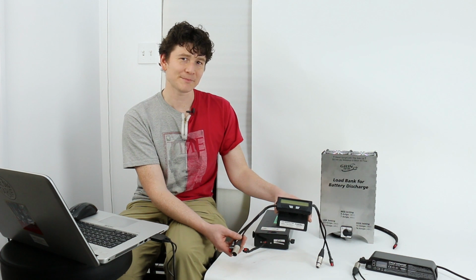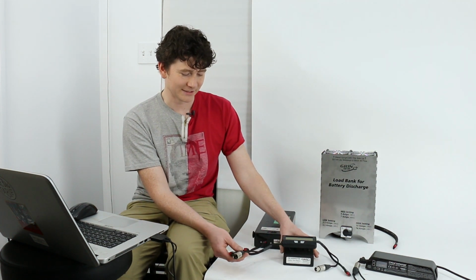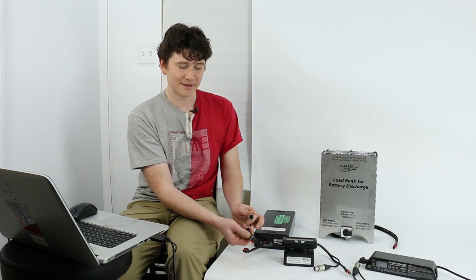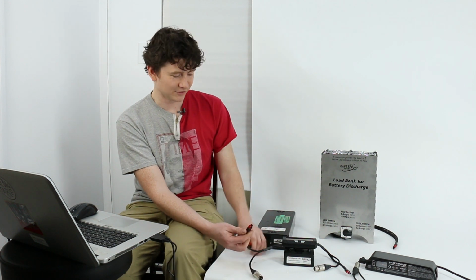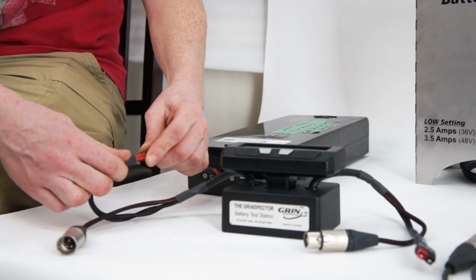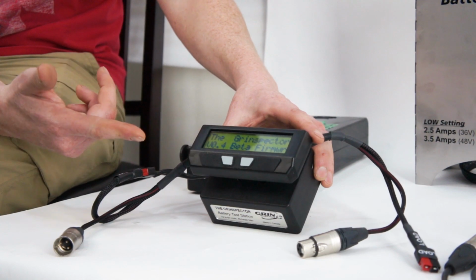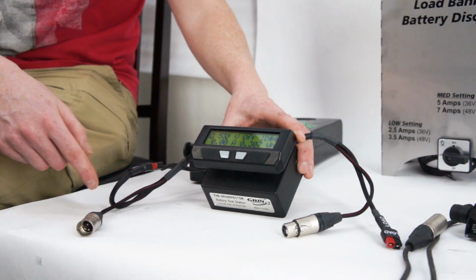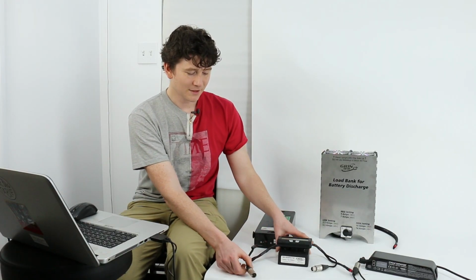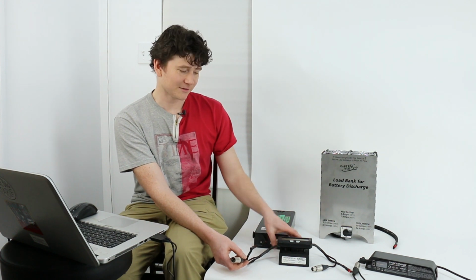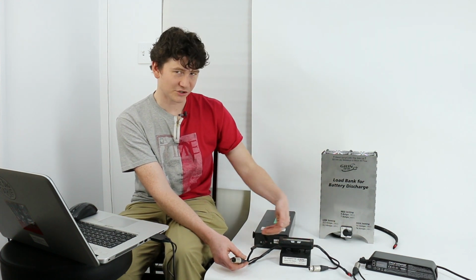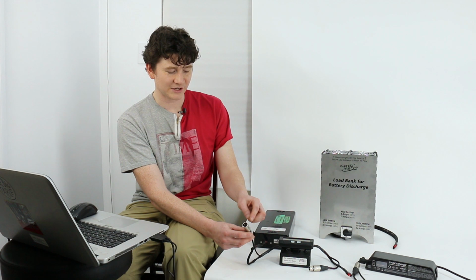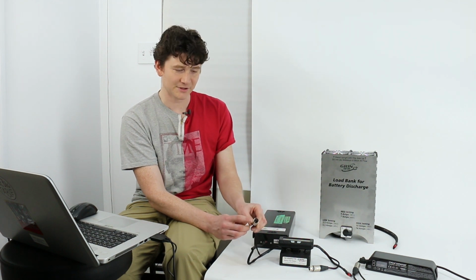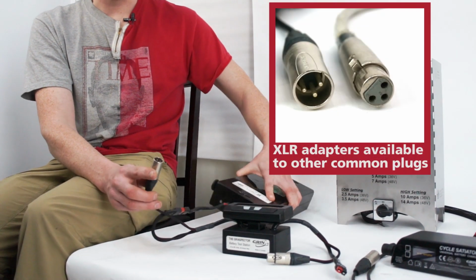The Grinspector acts as a liaison between these different components. On the input side, we have a plug for the discharge port of the battery. As soon as you plug a battery into the Anderson connector labeled 'battery,' the Grinspector station powers up, and this is where it discharges the battery from. If you're cycling packs, you also need to charge through the Grinspector, and the charging current passes through a separate plug using the 3-pin XLR standard, which connects to the charging port of your battery pack.